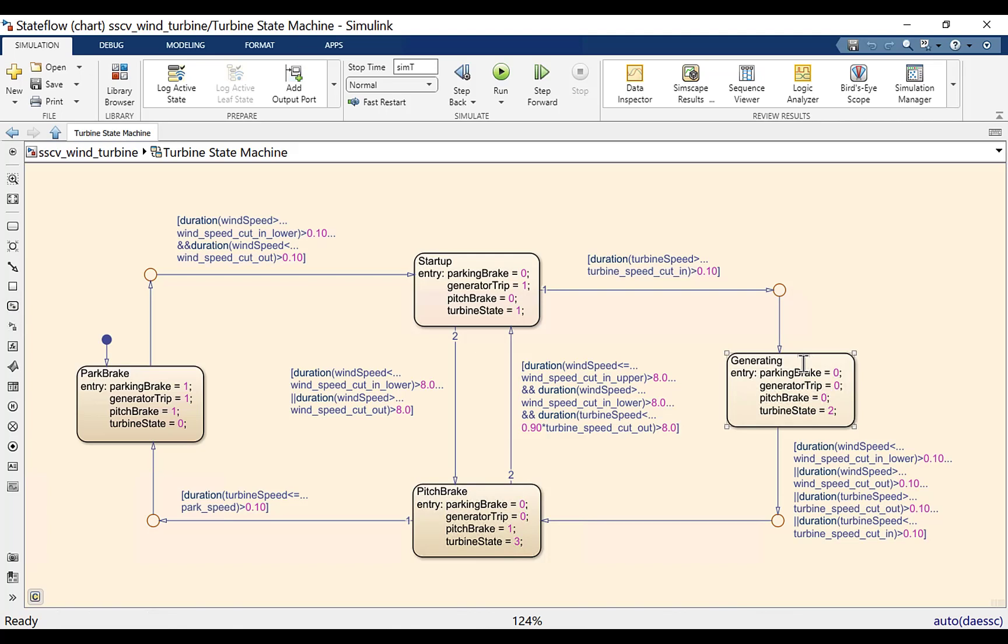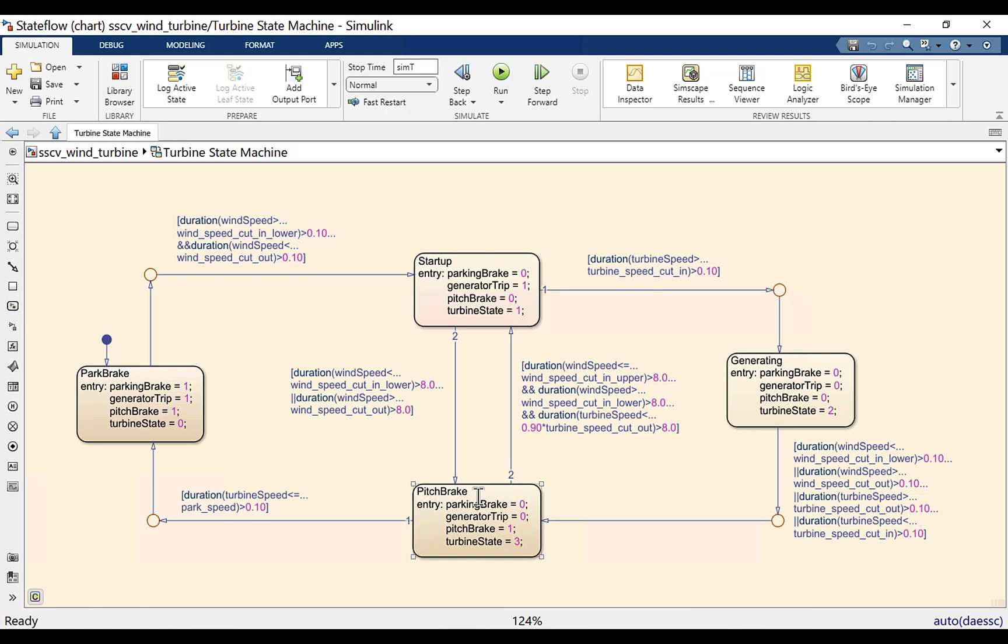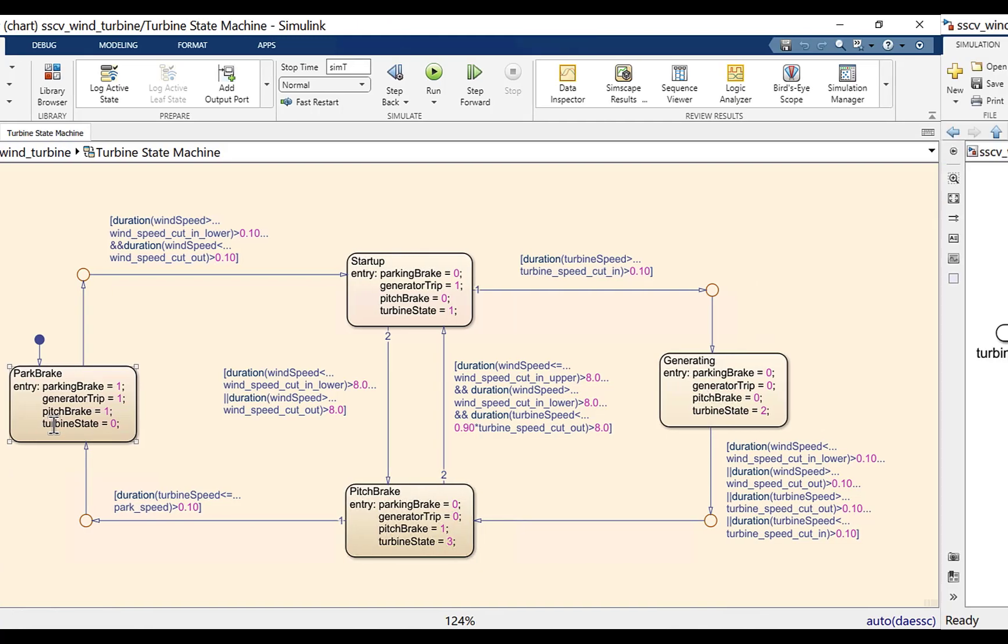If the conditions become unsuitable for power production or hazardous, turbine enters the pitch brake mode in which aerodynamic brakes are applied to the blade of the rotor hub. In the pitch brake mode, once the turbine speeds reduce up to the park speed, turbine enters the park brake mode where the hydraulic brakes are engaged with the rotor hub.